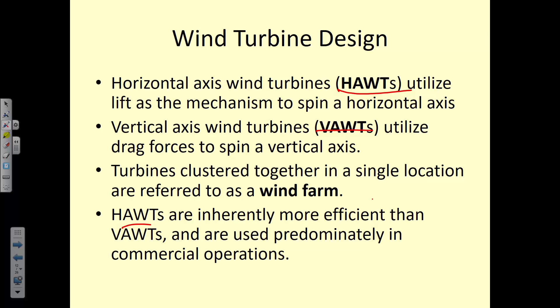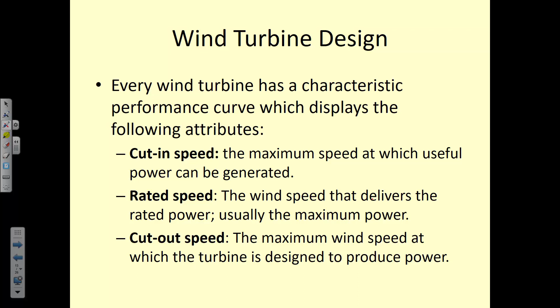And each wind turbine will have a characteristic performance curve, which displays three main attributes. The first is the cut-in speed, the minimum wind speed at which useful electricity begins to be generated. The rated speed, which is the wind speed that delivers the maximum amount of electricity, or maximum power. And then the cutout speed is the maximum wind speed at which the turbine is designed to produce power. And so the cutout speed is the wind speed at which the turbine, once it recognizes, because it's rotating at a certain rotations per minute and there's some mechanism in there that tells it what wind speed it's operating at, it puts on the brakes.